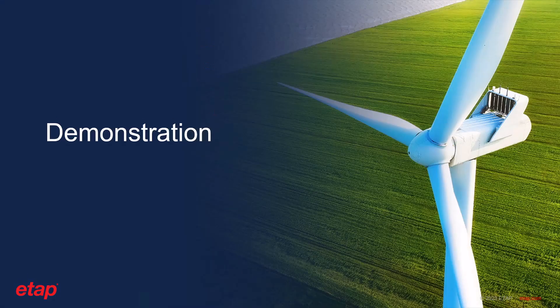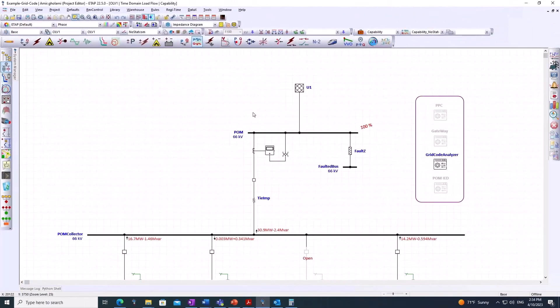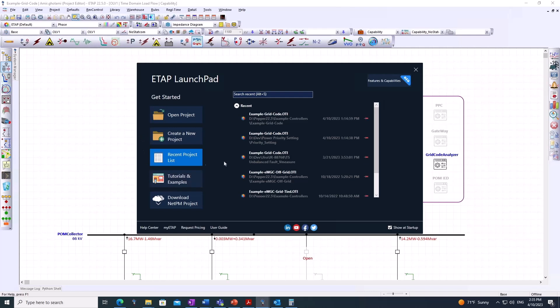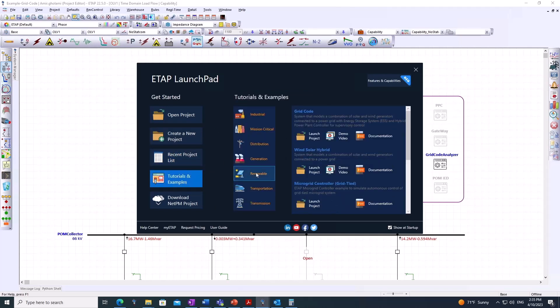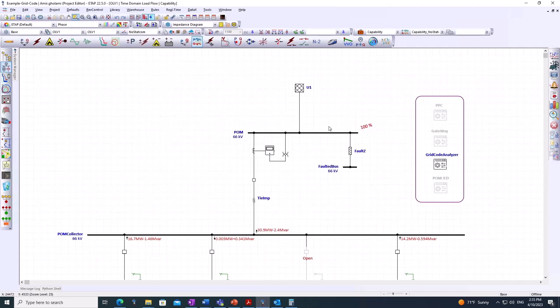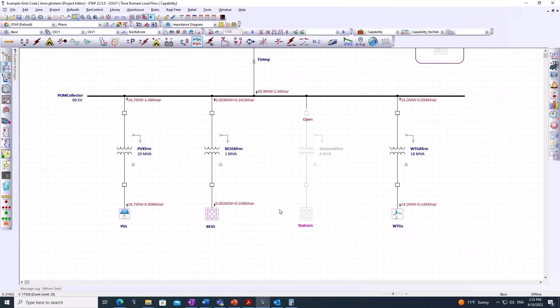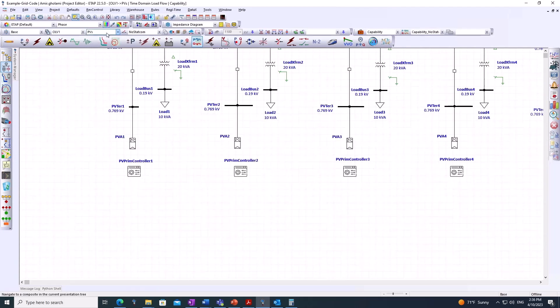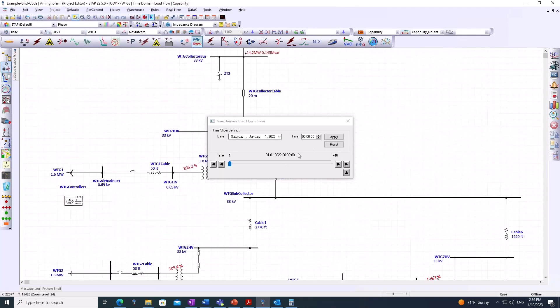Now we'll go through an actual demonstration within ETAP using a real example. An example project in the ETAP folder is specifically set up for grid code analysis. If the user opens ETAP, goes to tutorials and examples under renewable, there's a project called 'grid code.' Launching this project reveals a model of a power plant with multiple IBRs, including composite networks of PVs, battery energy storage systems, STATCOM, and WTGs, each of which may include one or more elements.